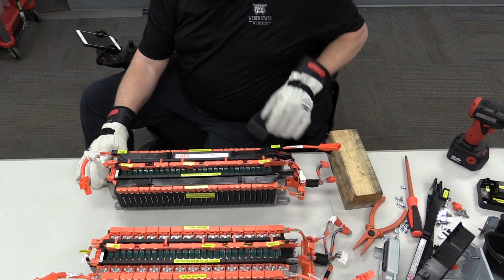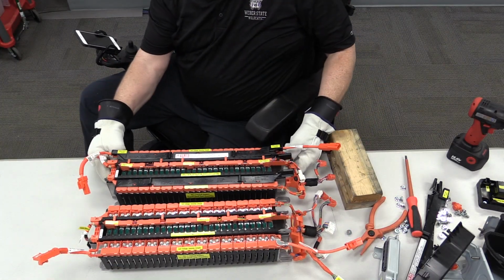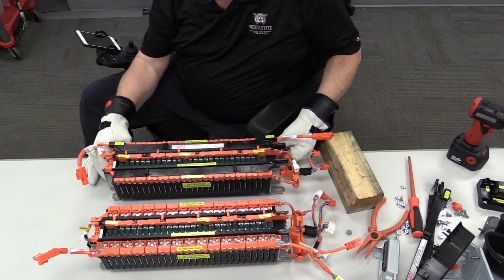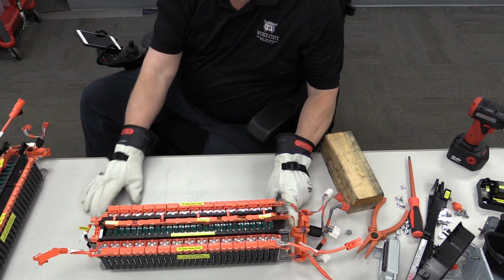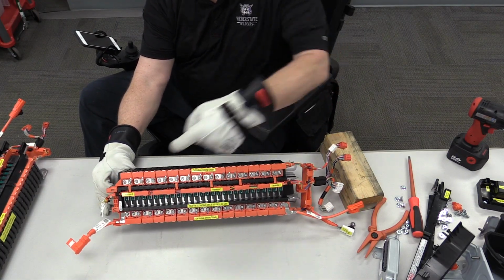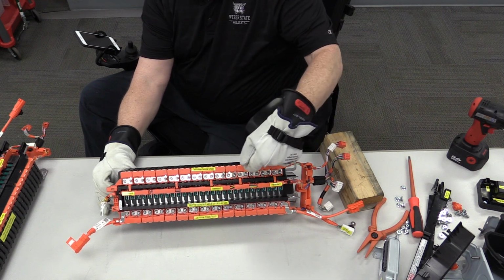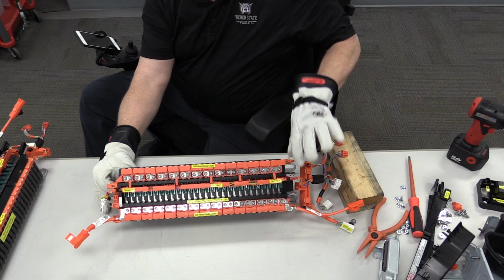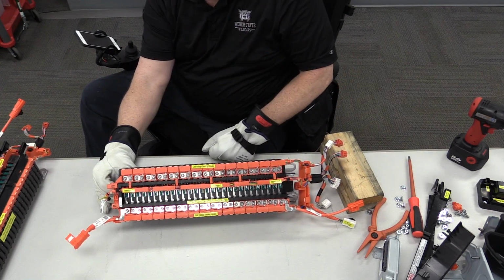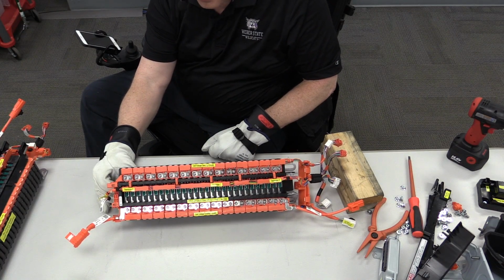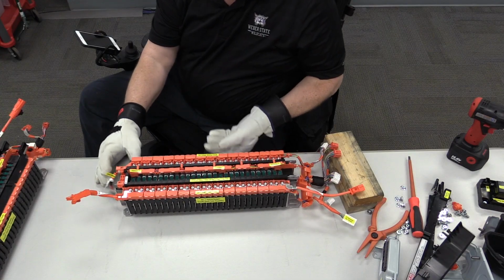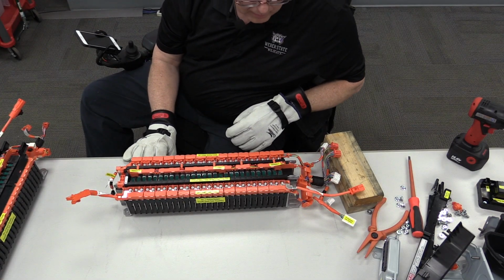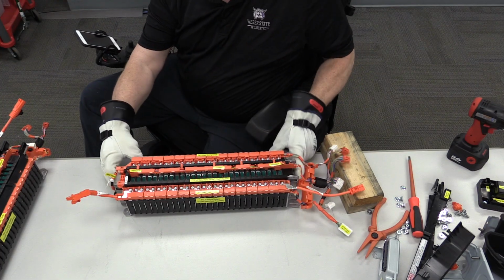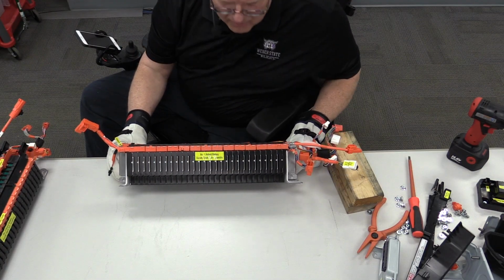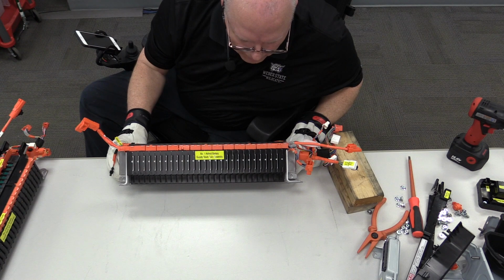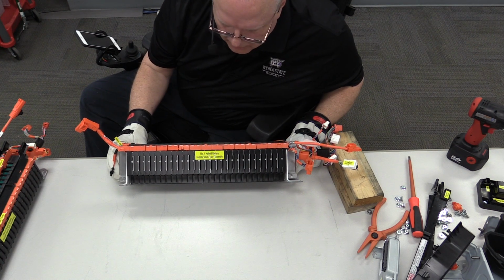Now, as you can see, 2 individual battery stacks, lithium-ion. If I get this one back out of the way, let's just look at this first one here. I'll tilt it a little better so you can see the nuts, the studs, the bus bars that connect those together, the individual wires for the battery voltage sensing going on there. I can't tip it over because we're not supposed to exceed the 80-degree angle, but as you can see, we've got plastic covers on the side to protect you from touching the battery cells themselves.